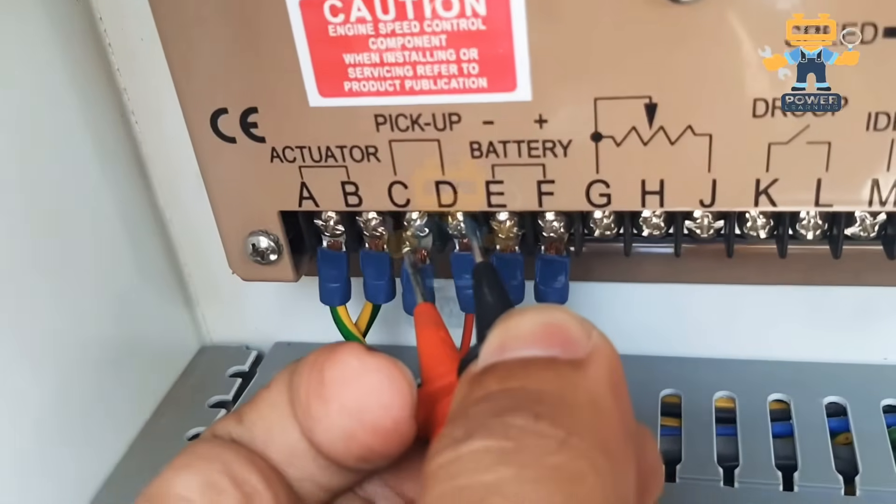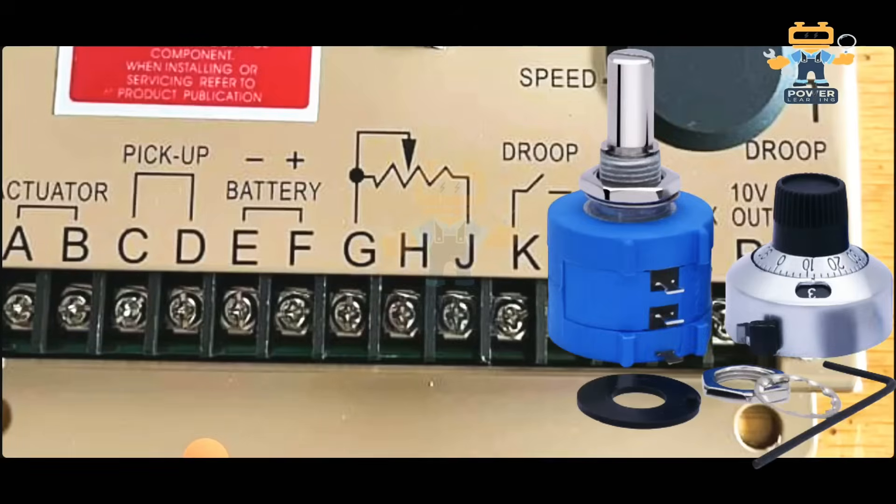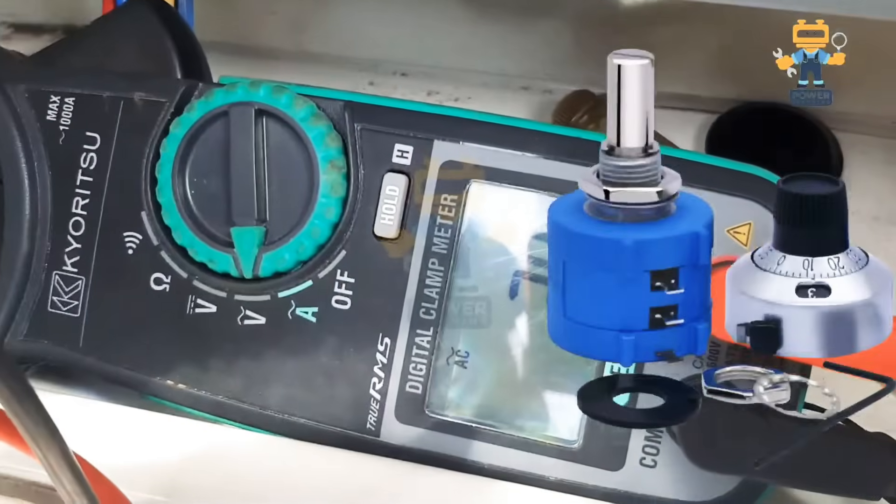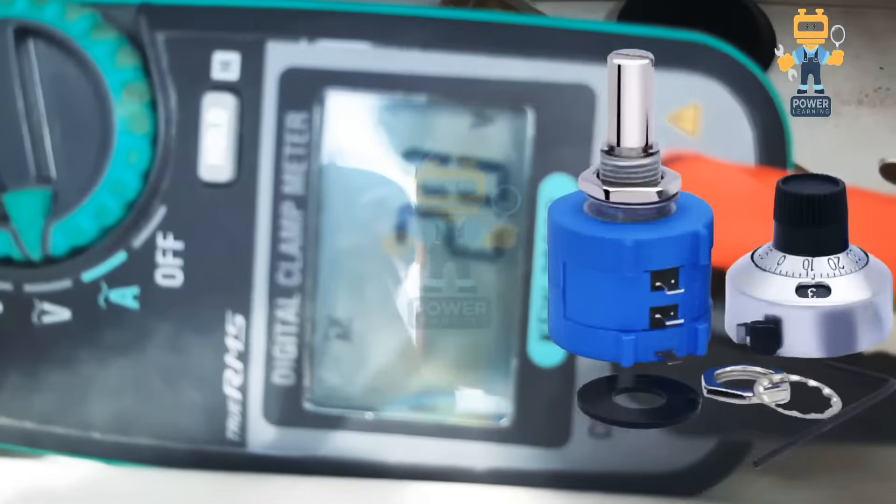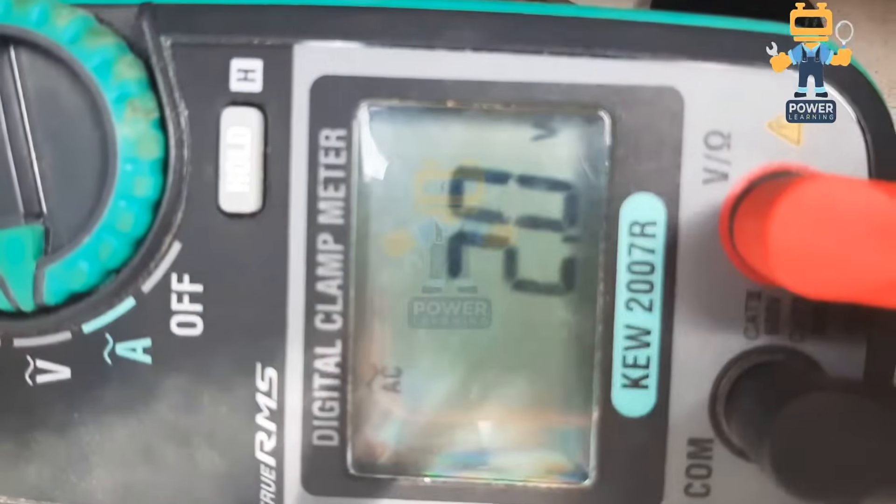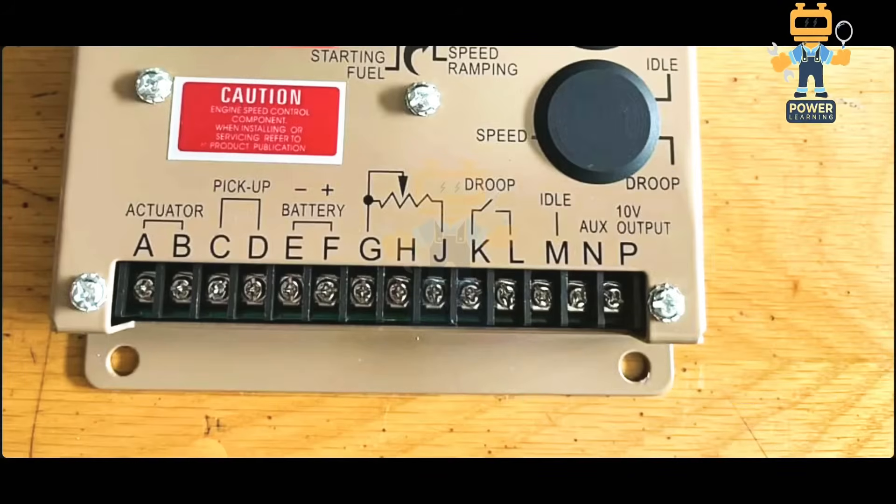This is the function of pickup and actuator. After that, here we have G, H, J. Here you see it's showing a symbol of a variable potentiometer. On these three terminals - G and J - these two terminals you will connect external potentiometer to set the engine speed plus or minus 10 percent from your control panel. You can install a variable 10 kilo ohm resistor so you can increase or decrease your engine speed.